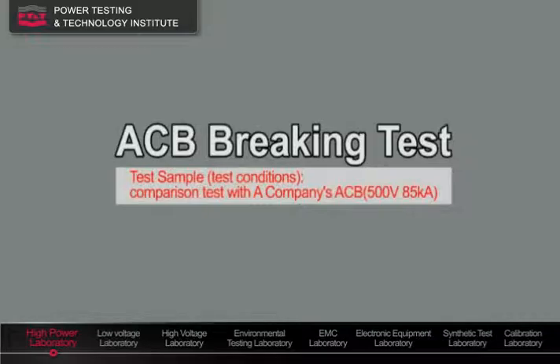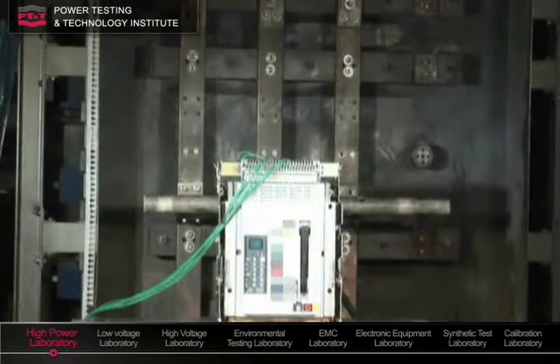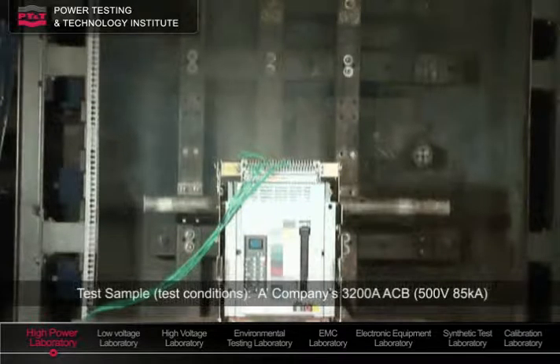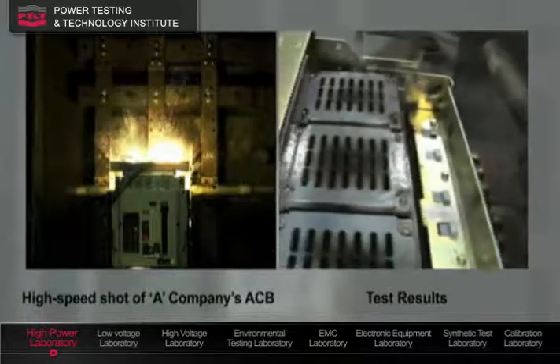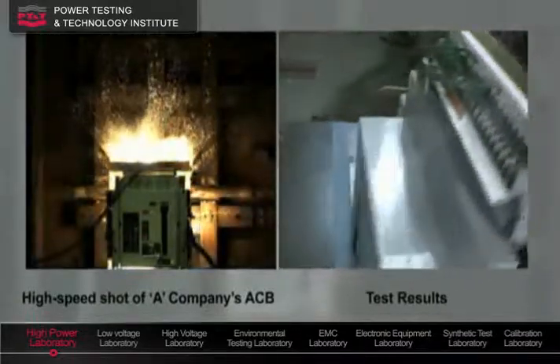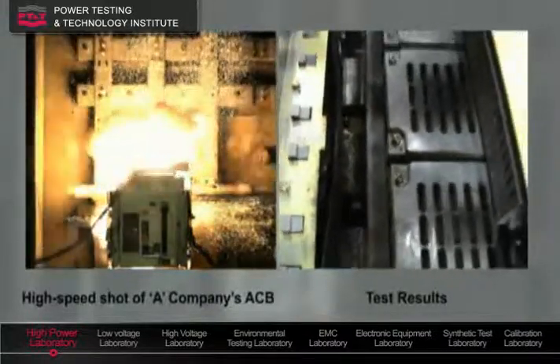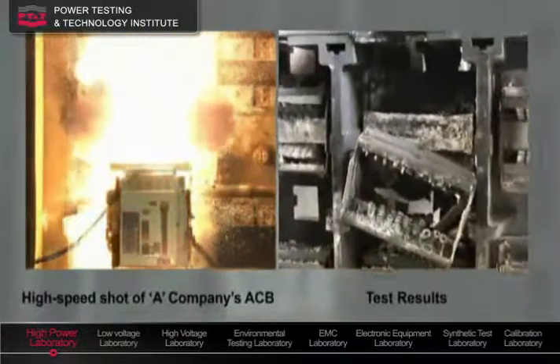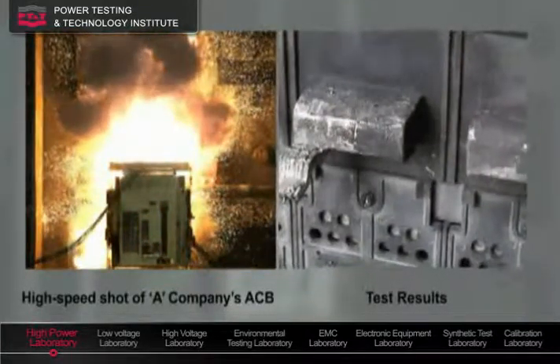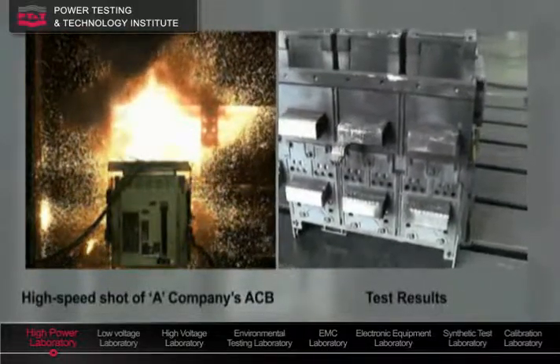This shows a failed breaking test of a competitor company's ACB. In the breaking test, the arc was not quenched but excessively flashed, and finally a line-to-line short-circuit occurred. The bus bar connected with the cradle melted, while the connection between the cradle and the main body was seriously damaged. The successive breaking tests could not be resumed.